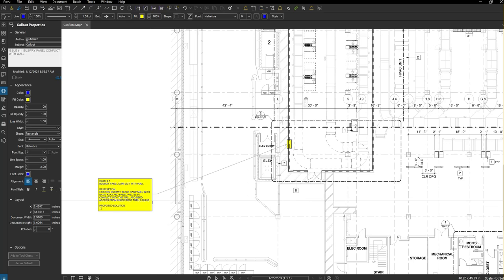Yep. So the first one is wall framing to box out for panel to intercept wall. The thing is, this is a rated wall, so that may be a problem. You see that? Right? And put: this is a rated wall, will need design team to confirm. And I don't know if this is true, right? Because obviously you got to lay out the wall, but let's say this is true.